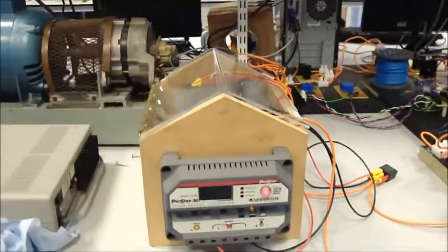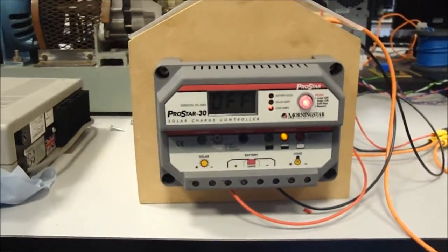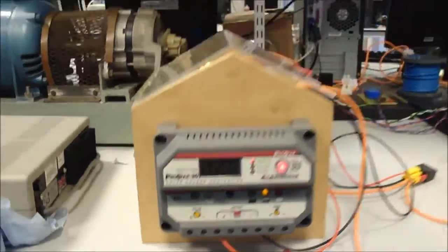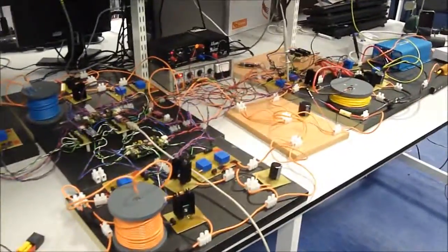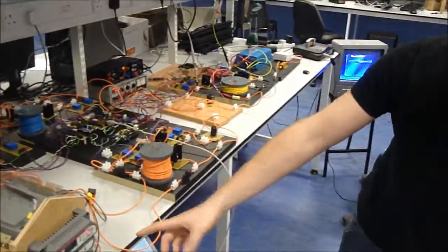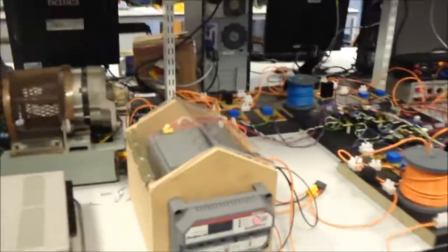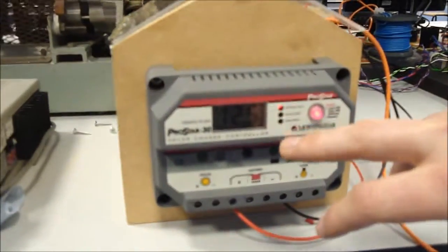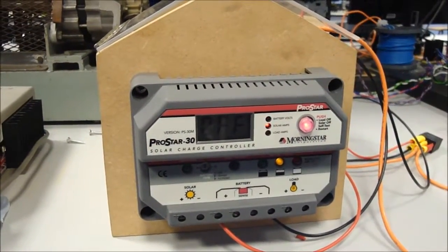At the moment, it is currently discharging the battery, so you won't be able to see it. But you can see as the wind generation starts to pick up, hopefully it'll go above. Yeah, and now because the wind generation has picked up, the load is lower, and it's now starting to charge. And you can see it's charging because the battery voltage is higher than it was before, and it's starting to increase.